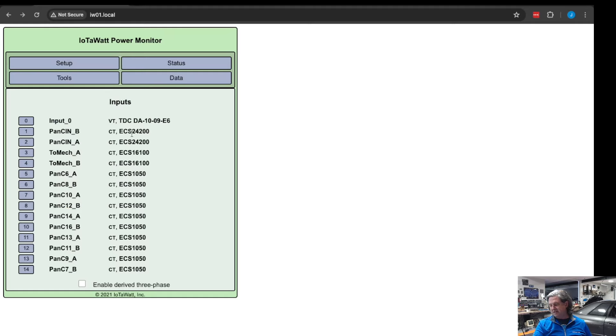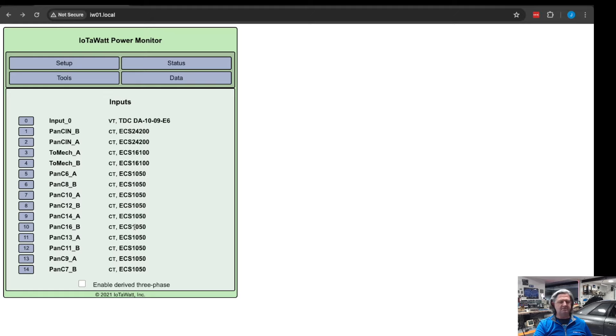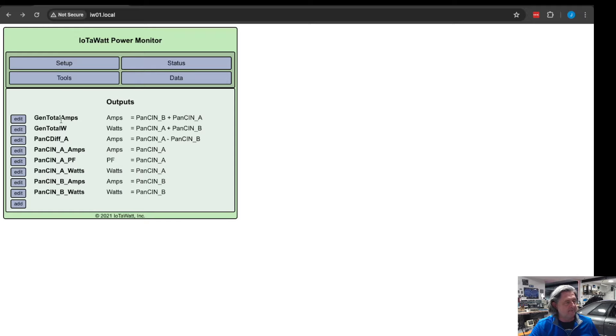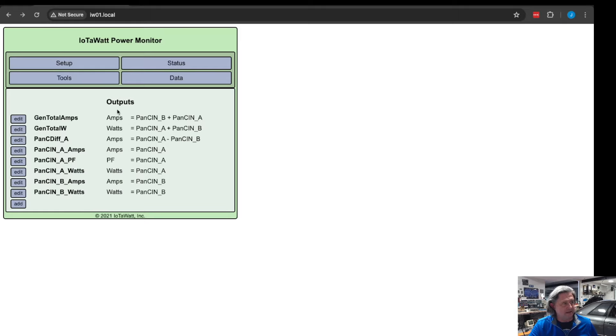Then simply you tell it, well it's got 14 inputs, you tell it what type of CT clamp you have on each of the inputs. So these are 200 amp, 100 amp, and 50 amp. It supports a bunch of different brands of CT clamps. You tell it what the inputs are and then it allows you to create some outputs that are things that are calculated.